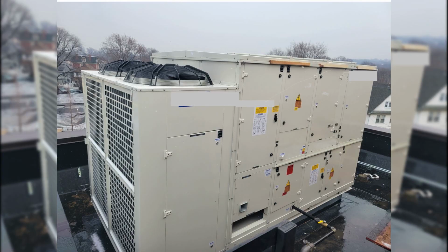15. New construction, major modernization. Multi-zone variable air volume DX heat pump units are the preferred choice for non-public assembly spaces like classrooms and offices. Public assembly spaces like gymnasiums and auditoriums should be served by custom single-zone variable air volume DX heat pump units.